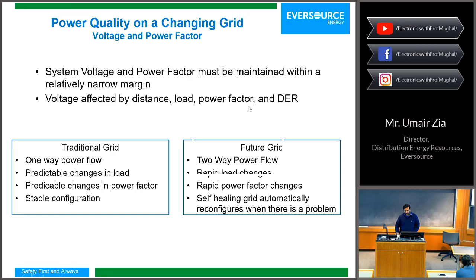A couple of those devices are at our major large substations on the transformers. The transformer output, as I mentioned, the ones you see outside, takes 13,000 volts and steps it down to 120. On our substations it's the same concept, a much larger system, but we don't want to set it at just one point because they're serving a lot of customers whose usage changes throughout the day in different ways.